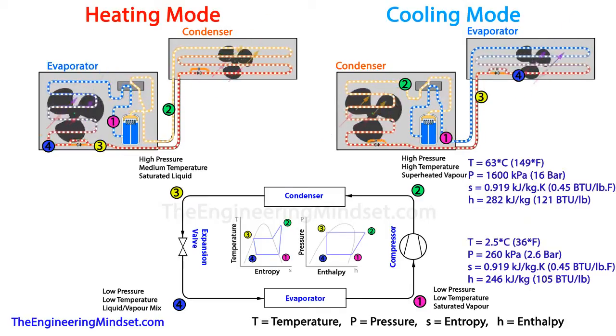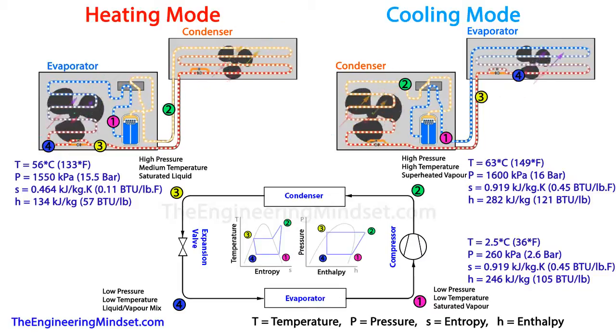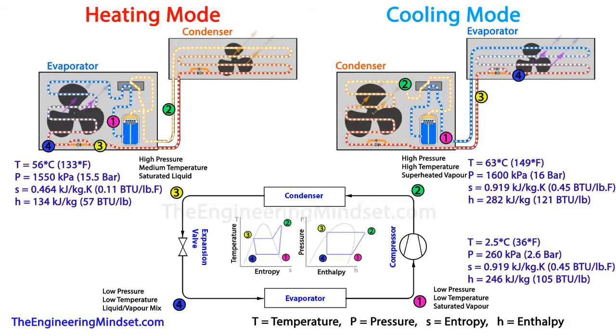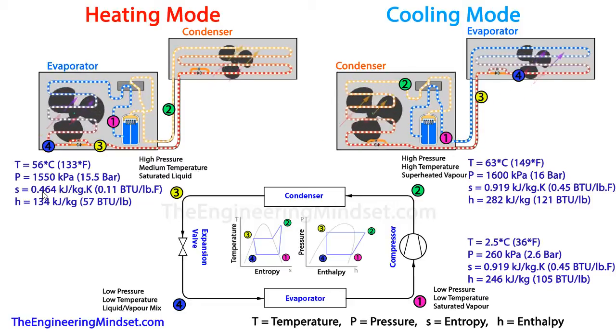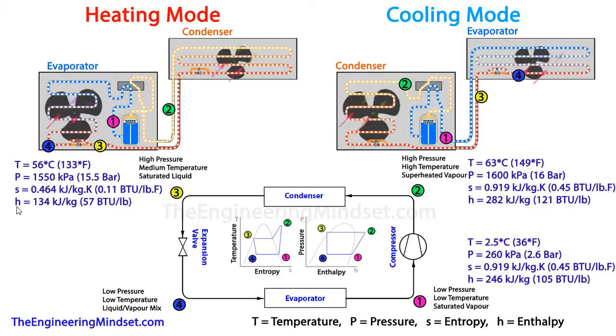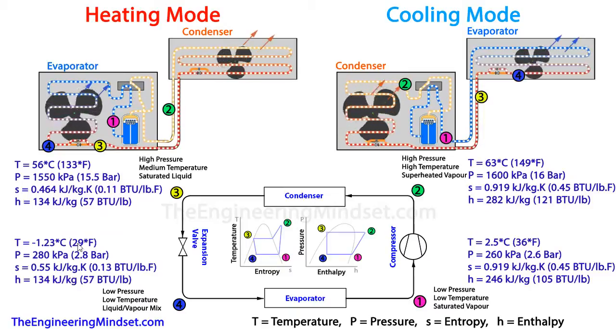At Point 3 there's some reduction in heat and also a pressure drop, because of the pipework and bends creating resistance to refrigerant flow. The temperature drops from 63°C down to 56°C (133°F). The pressure sees a small reduction of 50 kPa — about half a bar. Entropy has also reduced, nearly halving to 0.46 kJ/kg·K (0.11 BTU/lb·°F), and enthalpy has dropped from 282 down to 134 kJ/kg (57 BTU/lb).